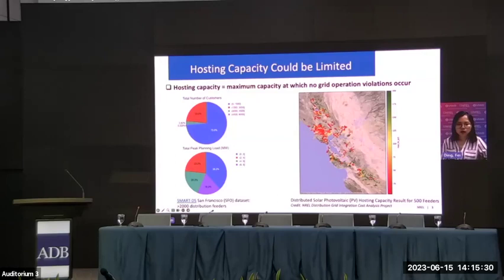The red figure shows the result of 500 feeders. The hosting capacity results for these 500 networks differ a lot. But as shown in this figure, many of them have very low hosting capacity, which can only afford PV capacity less than 25% of peak load.